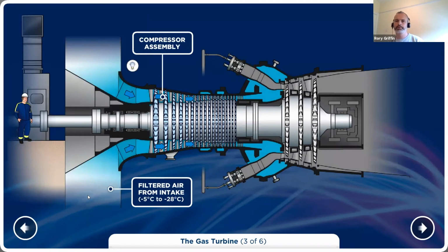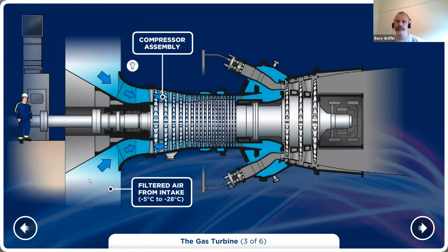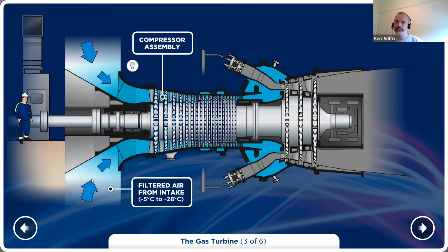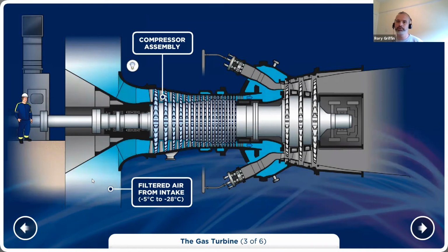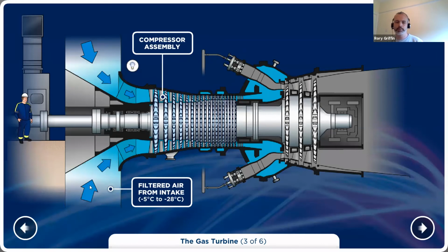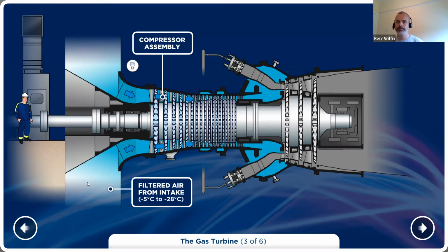So what we've done so far is we've drawn air in through the filter house. It's about 600 kilos per second, or I suppose 2,200 tons of air per hour is what's coming into the machine. As it comes in through the filters, you get a drop in pressure and temperature. During operation, something we do keep an eye on is the differential pressure across the filters. If the filters are starting to clog, the differential pressure will increase. So that's a kind of a performance metric you keep an eye on.